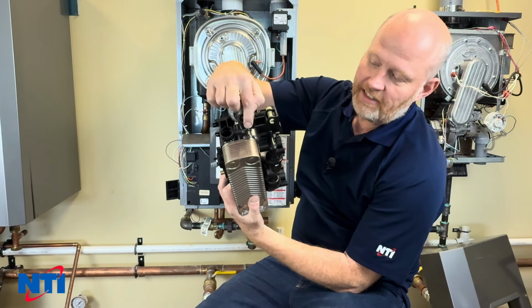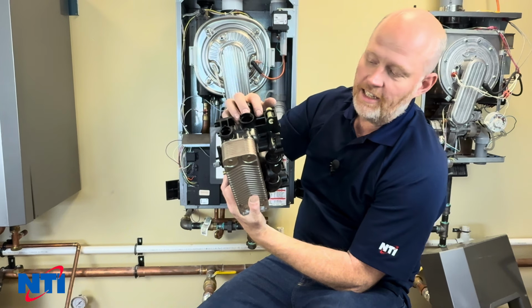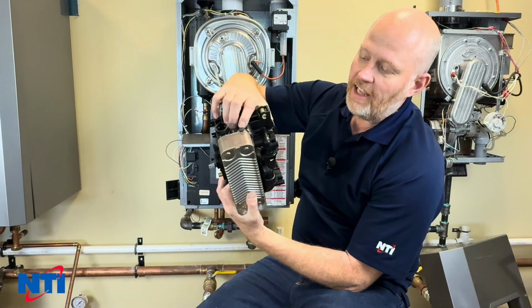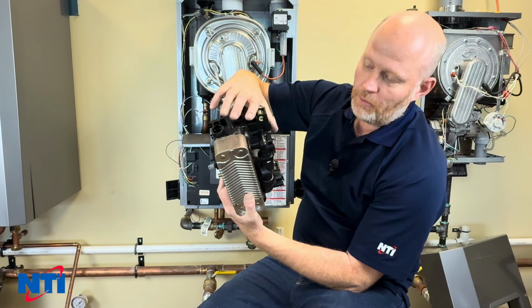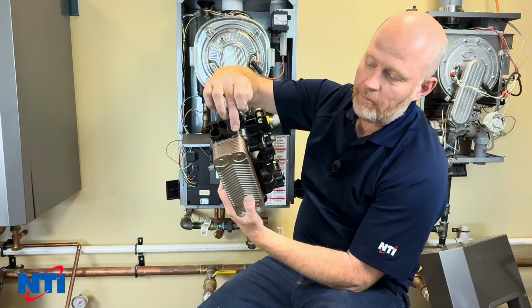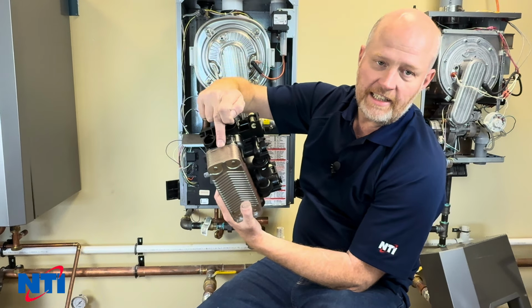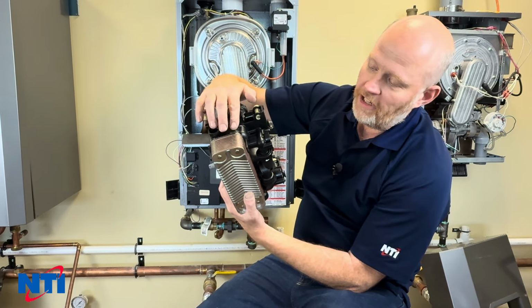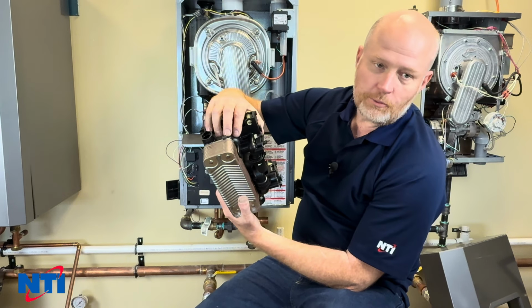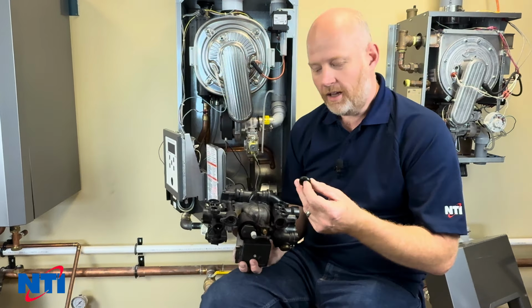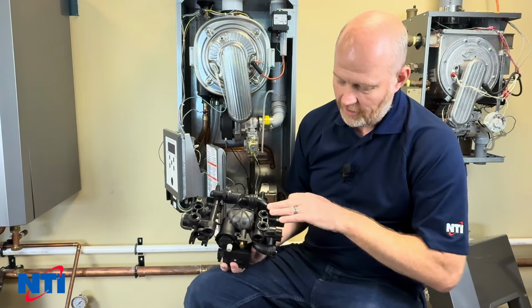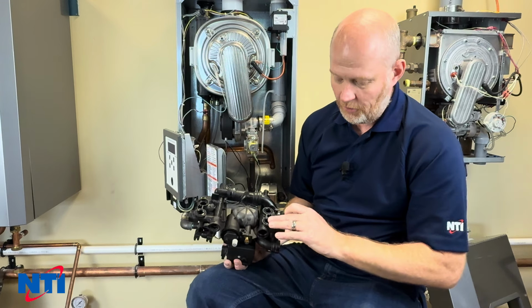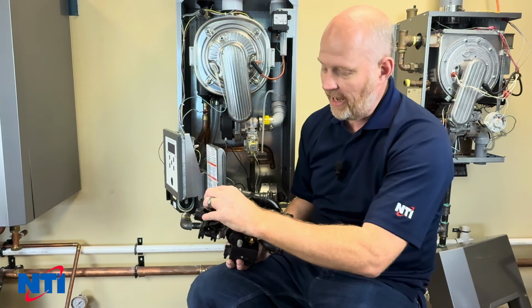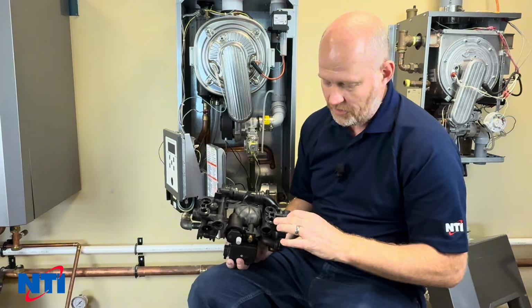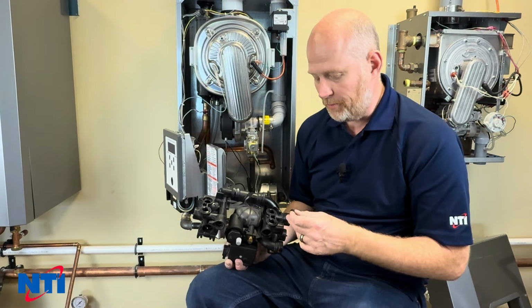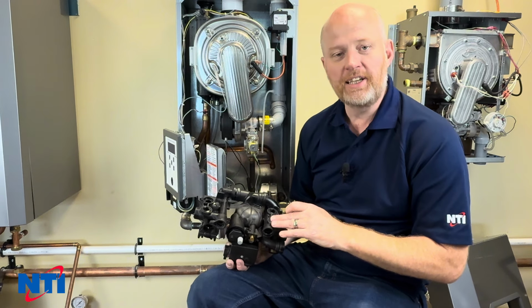You can see the plastic tab sits just over the lip of the plate exchanger. If you were to try and stick this in backwards, what would happen is you would butt up against this and you'd have a lot of trouble tightening up this screw. So make sure that you put the short side to the left when you go to reassemble. So the 4 gaskets that I was referencing are these 4 here. When it's out of the boiler, obviously it's easy to see, and they just push into these holes. And again, a little bit of grease can help hold them in place when you're taking apart and reassembling your boiler.